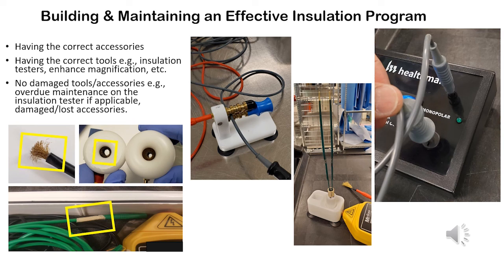where that is a brand new one. And then repairing your own tools, which is not good. And in this case, they're repairing the grounding cable, and you can actually hurt yourself. And then also making sure that your tester is not overdue for maintenance. And typically they can range up to 1 year before you need to make sure they're recalibrated.